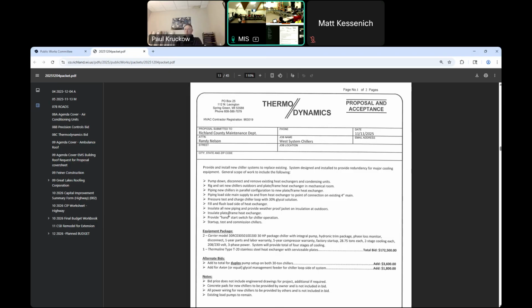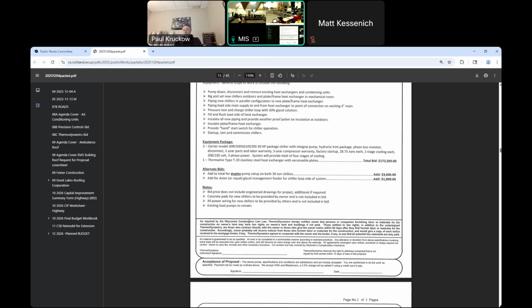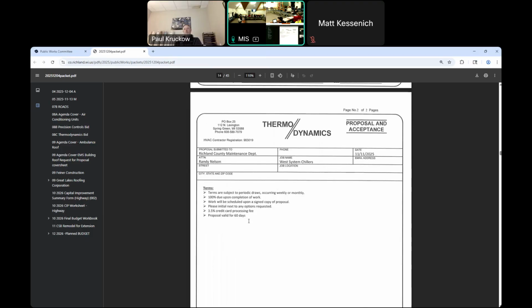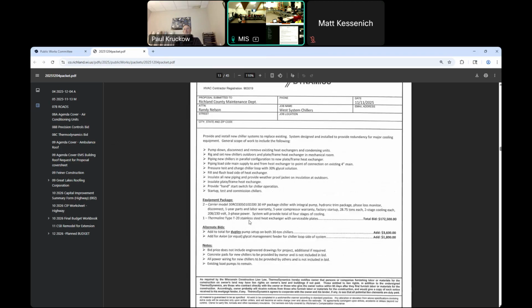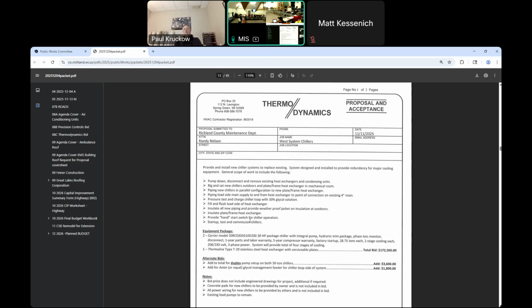So not knowing, the concern of the refrigerant is one of mine, being in the building versus outside the building. I don't know the exact quantity of the Multistack chiller, but I know for sure the refrigerant's in the building because you're piping it to the condensers outside. With that many circuits, you may be beyond the threshold. I don't want you to get a surprise afterward, when the inspector comes in and says, okay, where's your mitigation? That is a sensor and an exhaust fan, and where do we get the air in, that kind of thing. There is something to it, and we've been made keenly aware of that by the manufacturer.